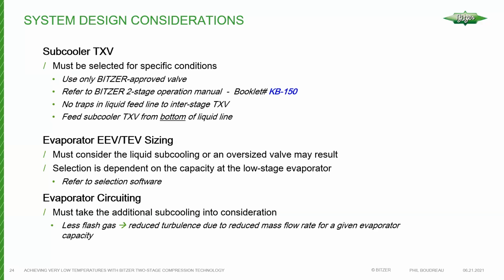But if you forgot to include the effect of the subcooling, the additional capacity that you get using subcooling, then it's very easy to oversize a valve. And as we know, oversized valves can lead to, and will lead to, hunting. Hunting leads to poor control of the evaporator and the possibility and likelihood of liquid refrigerant traveling down the suction line. And again, these are direct suction compressors. So the capacity of the main expansion valve needs to take into consideration the capacity of the evaporator and the operating conditions, but we never, ever want to forget that subcooling.